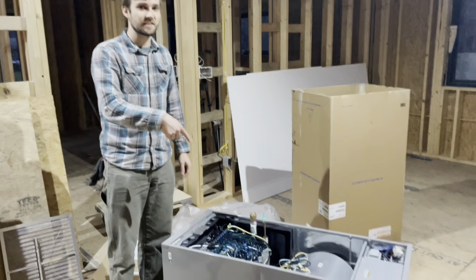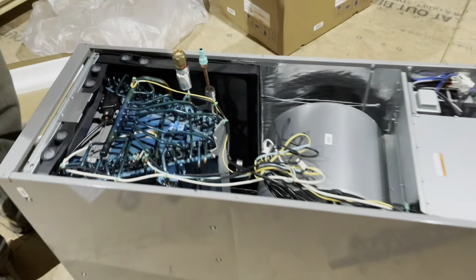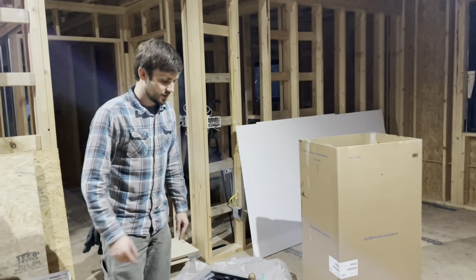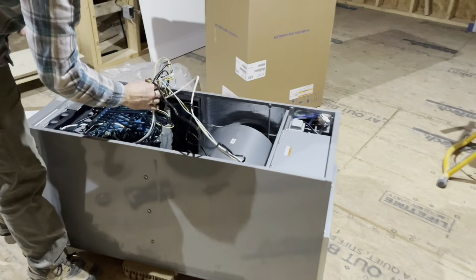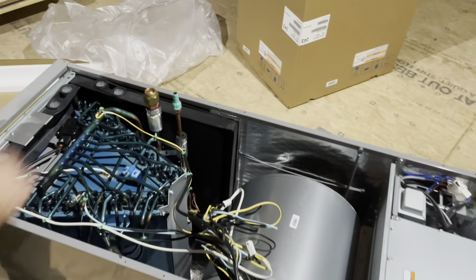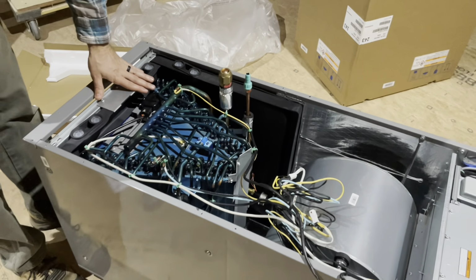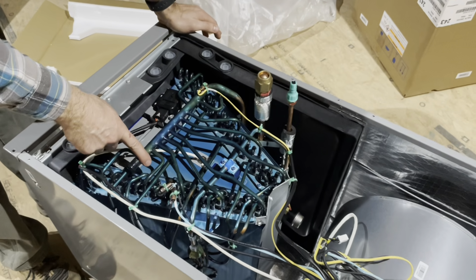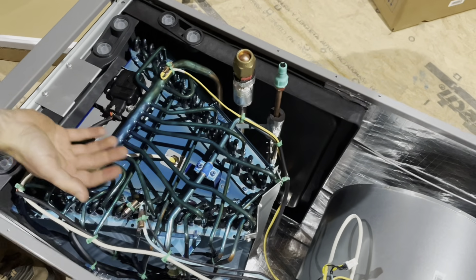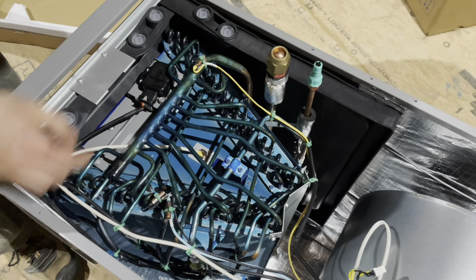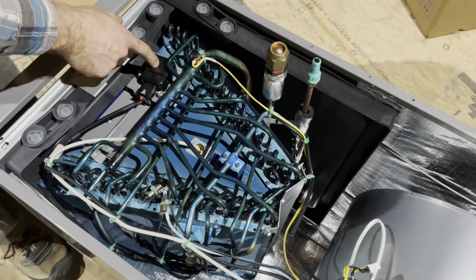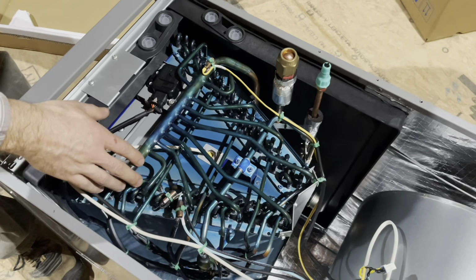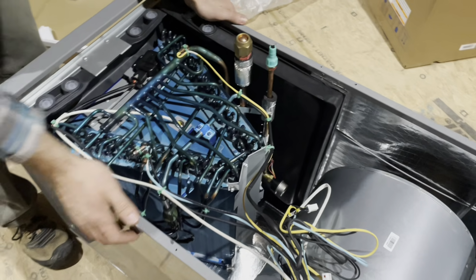We just got the unit in, and I'm unboxing it and converting it to downflow configuration to fit our use here. I just need to pull this coil out, flip it 180 degrees, and put it back in. So I cut all the wire ties holding that together to give me some slack to flip this. This is one of those new coils that has R32 and it's all painted blue - not entirely sure why. It has a refrigerant sensor there to shut off if there's a leak, because it's flammable. Kind of weird looking.